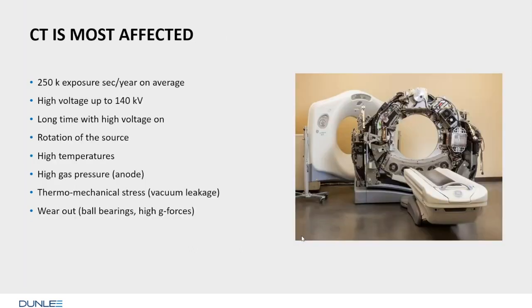CT is most affected. You see here from a refurbished operation, a CT system without covers, and you see an X-ray tube here. The thing spins. You know that CT is affected because the on time for high voltage is pretty high in CT, orders of magnitude higher than in angio and in general purpose radiography. So the electric fields are on much longer per year than in other modalities.